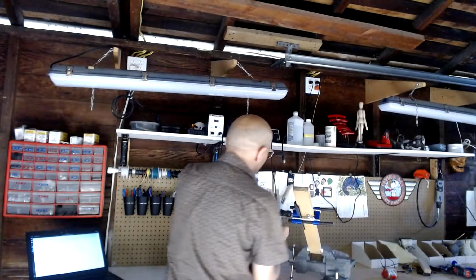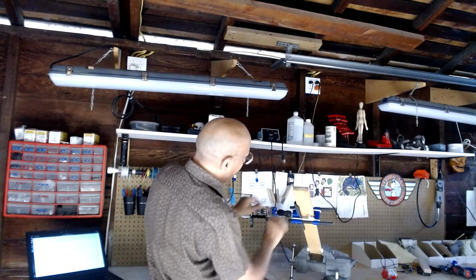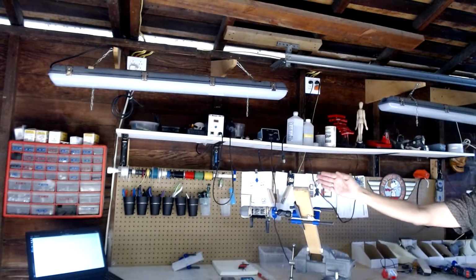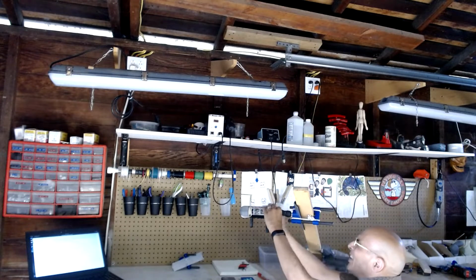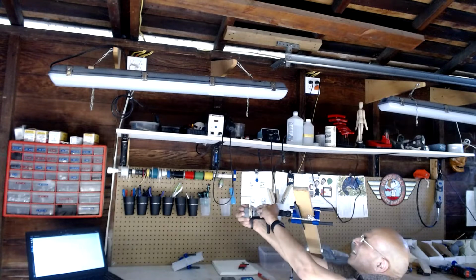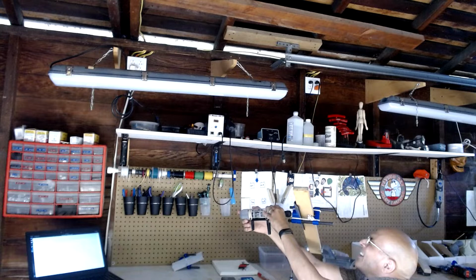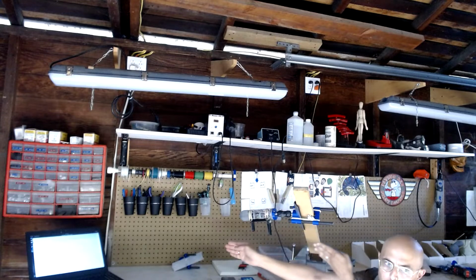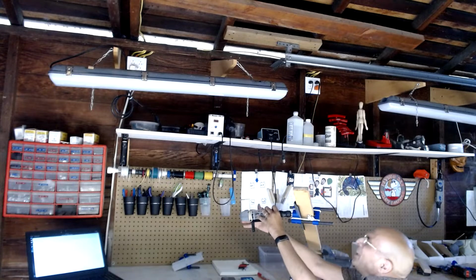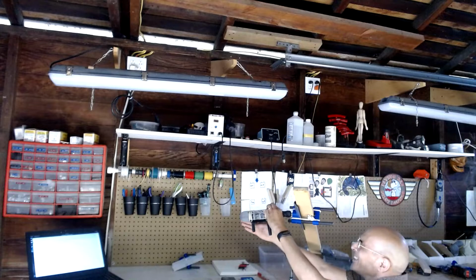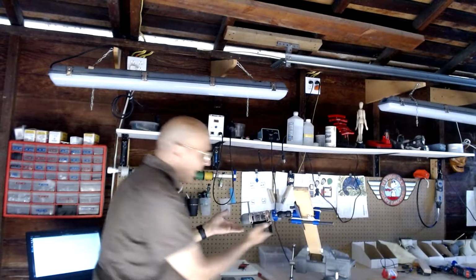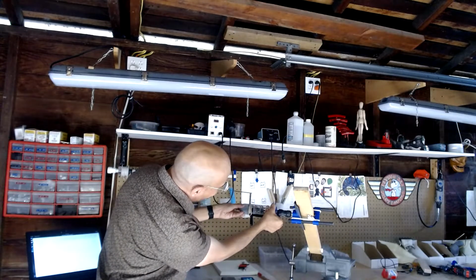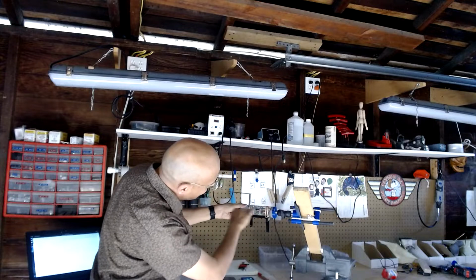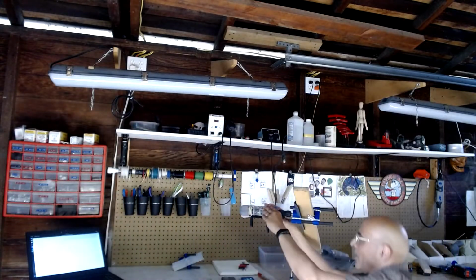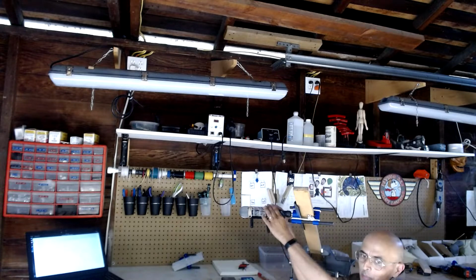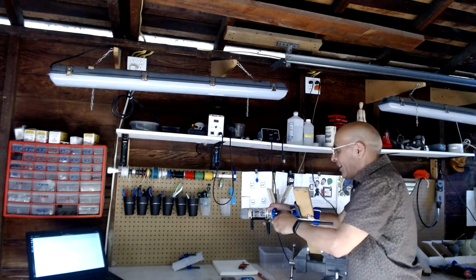So we'll put it back, and I'm going to pretend that this is my strut, and I've actually tightened the screw, and I'm going to sight at my distant object and look down these sights, loosen the mount a little bit, twist the probe so that the spirit level is level, use the sight to sight down at the object, moving my head up and down as necessary because the object may be high or low in elevation, and then in the process also look to the side. Notice how my probe is lying, set it up so that it's about down the center line of the fuselage, just down some kind of center line you can see that makes sense, and then go back and make sure that all the other adjustments are working. And eventually you should be able to get it to a point where it is well aligned, and then tighten this, and you're good to go.